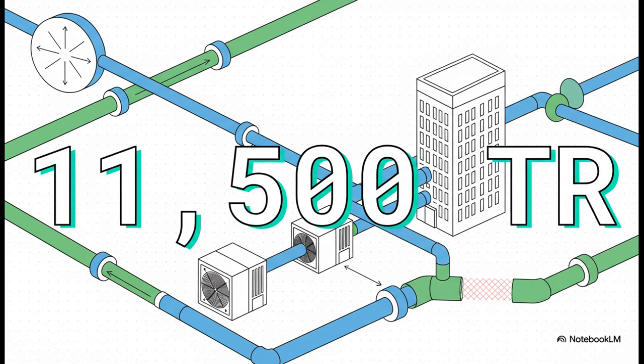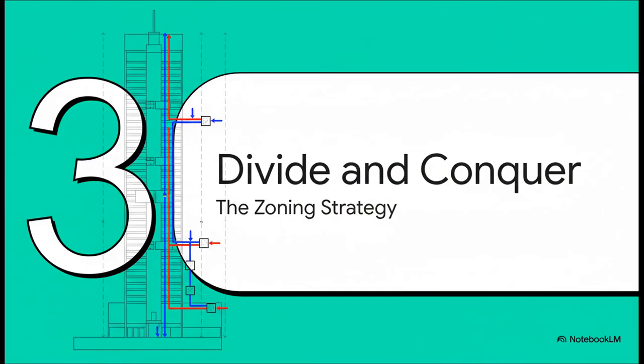This is what our cooling plant, whether it's our own chillers or a feed from a district cooling plant, absolutely has to deliver, day in and day out. Okay, so we've got our cooling number, and we know we can't use one giant loop because the pressure would blow it apart. So what's the solution? Well, it's actually a really elegant strategy.